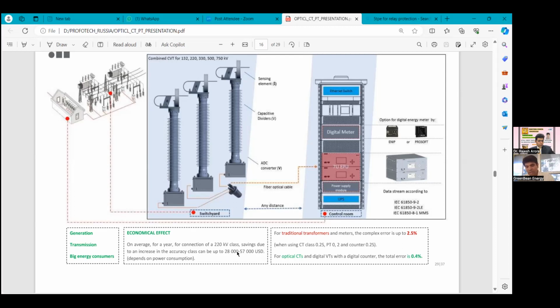With the traditional transformer and meter, the complex error is up to 2.5% when using CT 0.2S, PT 0.2 and counter 0.2S. For the optical CT and digital VT with the digital counter, the error is 0.4%. So here it is 2.5%, and in comparison only 0.4%.